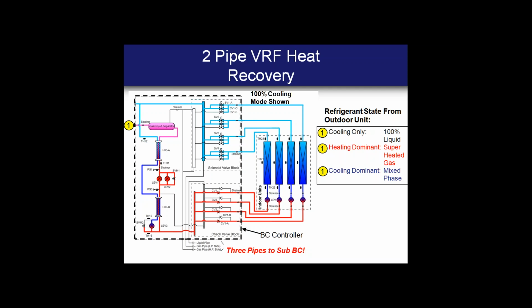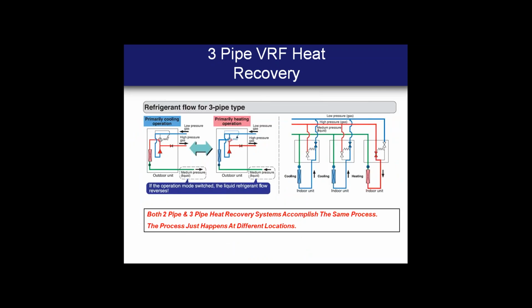Also, what's unique is when you have units in heat, that liquid is recovered and brought back to this BC controller and actually sent back out to units calling for cool. So that liquid is reused in series, and that's the mechanism of heat recovery. Again, when you look at three pipe variations from other manufacturers, they're accomplishing the same task, but they're actually doing that back at the outdoor unit.